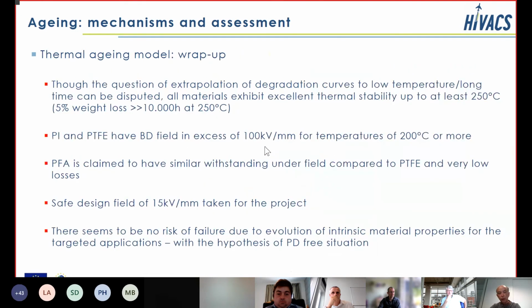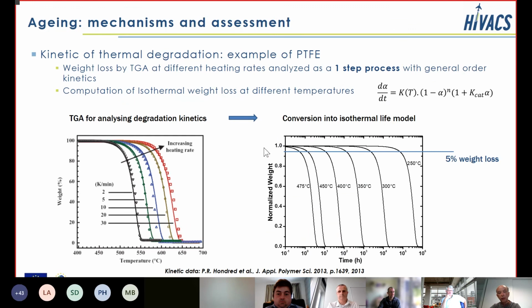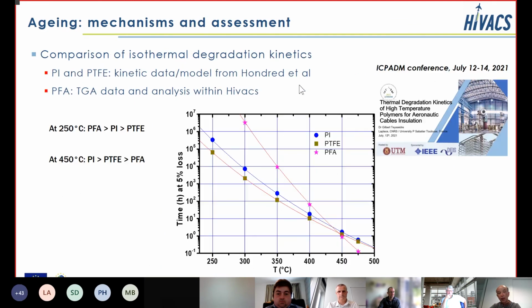With this data, we used data from the literature for PTFE and polyimide, and we performed our own TGA measurement, done by Nexsense, on the PFA material because there were no literature data on that. And here there is a comparison of the weight loss as a function of temperature, as predicted by the model, comparing PI, PTFE, and PFA. From these results, which of course have to be checked by experiments, PFA would have better thermal withstanding than the other two materials, due to an apparently higher activation energy for the degradation. That will be presented in the next weeks at the ICPADM conference.